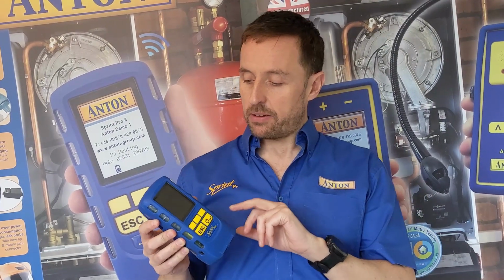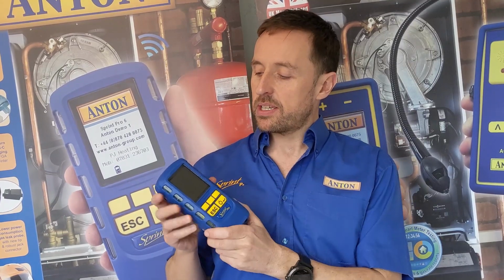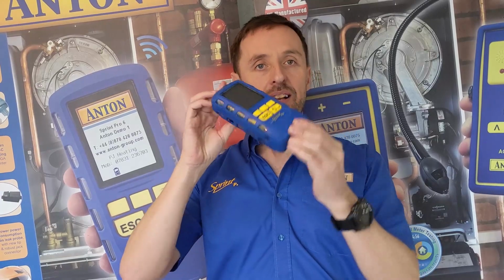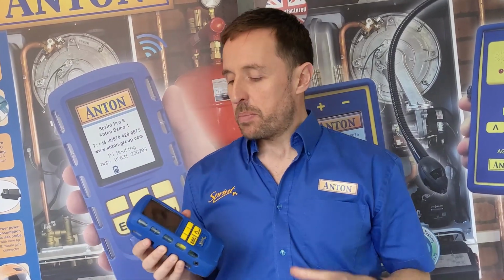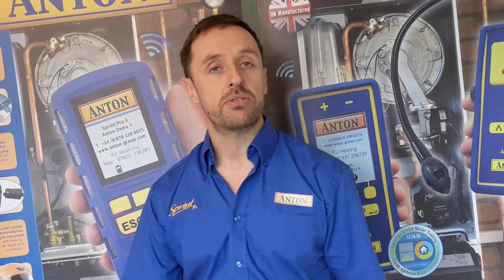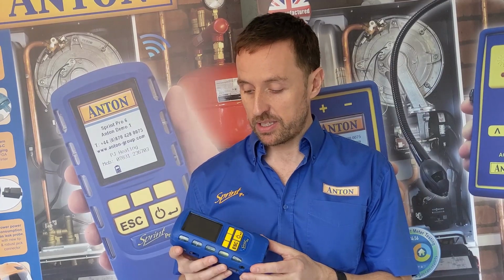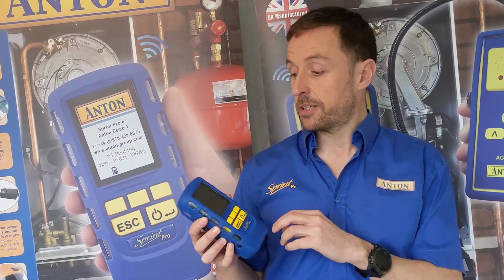Okay, but it's important that you get it sent in. What I will say is you can send in just the instrument, so just the handheld, this piece. Obviously, if you're sending it in directly, packaging up yourself, that's easier because it's easier to package up. But we recommend you send the whole kit, so all your probes, your chargers, even your leak detectors, things like that, because we will test everything, and it doesn't cost you any more or less if you send in the whole kit. Often, if there is an issue with an analyzer, it's usually the flue probe, not the analyzer itself. So if we see everything, we can test it together and make sure it's all working perfectly. You just get better value for your annual calibration, basically. So obviously it means a bigger box, but we still feel it's worth it. So that's one thing to consider.